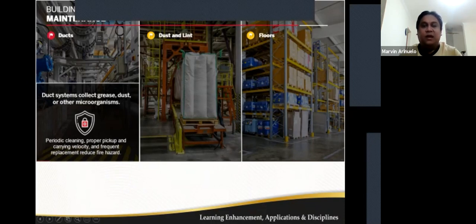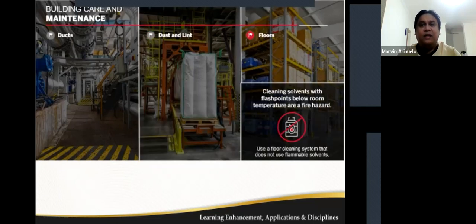So another concern in the building care maintenance is your dust and lints. Do you know that it takes about 3 mm of dust or lint to create a fire or explosion hazard? The flash fire can occur when there is as little as 0.8 mm of finely divided dust from wood, food products, paper, and the like. Therefore, it is essential that facilities remove combustible dust and lint accumulation from the walls, the ceiling, and exposed structural members.